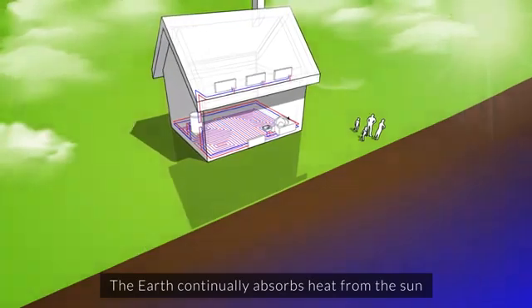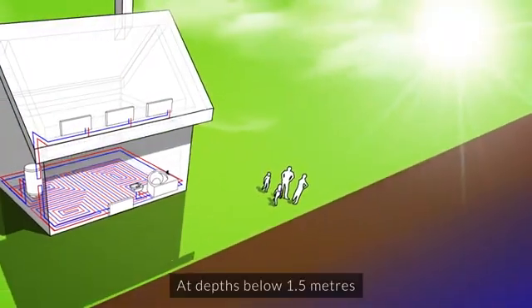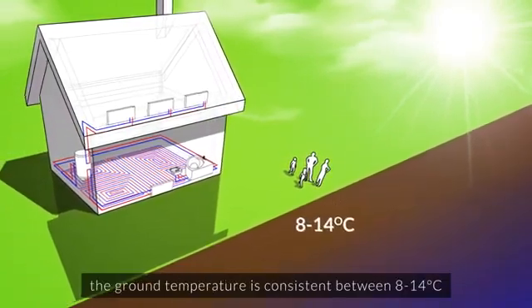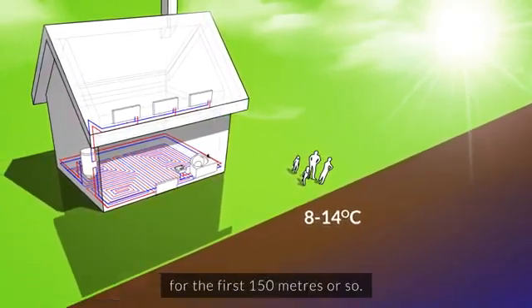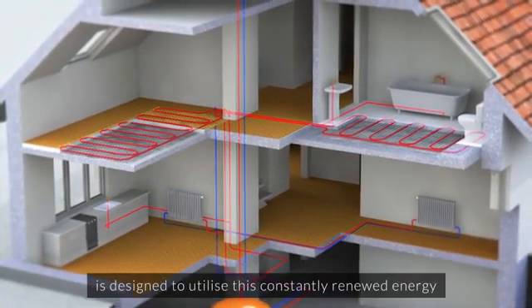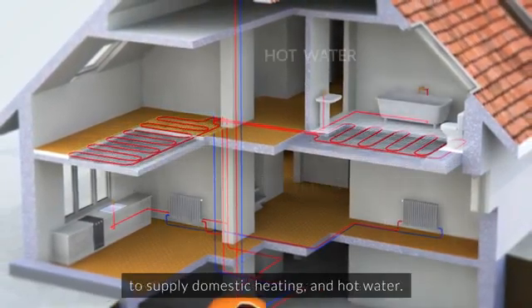The earth continually absorbs heat from the Sun and stores it in the ground below the surface. At depths below 1.5 meters, the ground temperature is consistent between 8 and 14 degrees Celsius for the first 150 meters or so. The ground source heat pump is designed to utilize this constantly renewed energy to supply domestic heating and hot water.